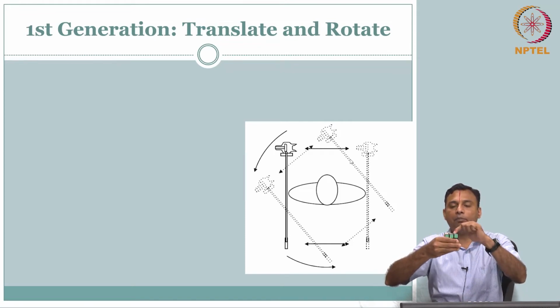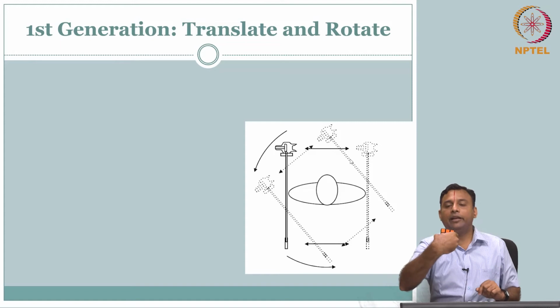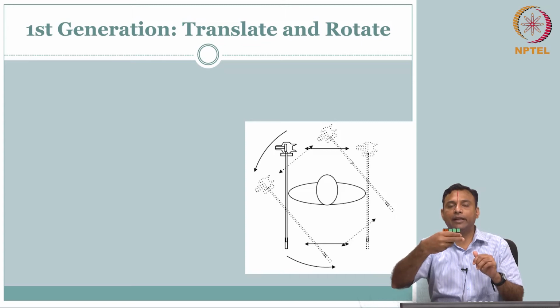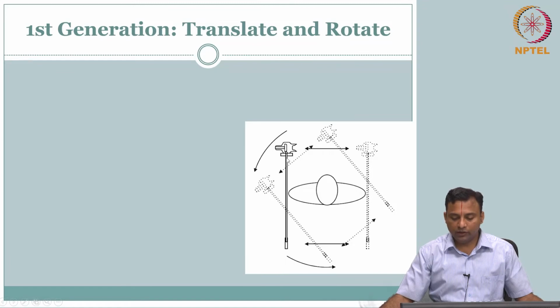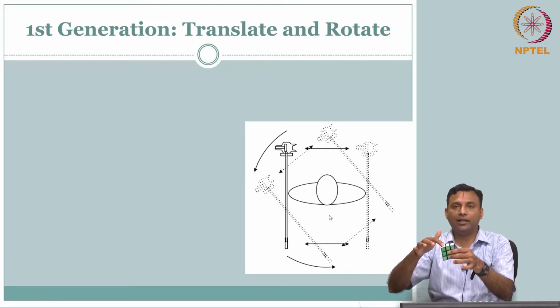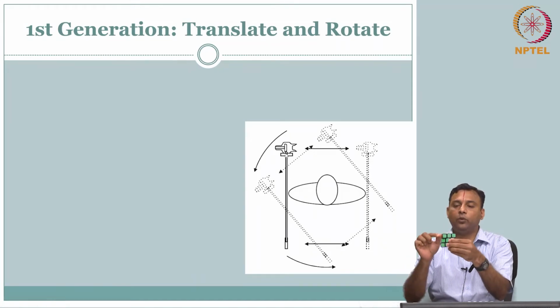Now I want the same tissue region, so I have to view it from a different location. You can rotate, the 90-degree rotation is simple, right. You can step in any direction, any step size for different views. This is what we call a pencil beam, a very narrow beam, like a pencil. Now if I have to scan the patient, and get this 3 cross 3 in this example, I am going to get only one slice, the one row.